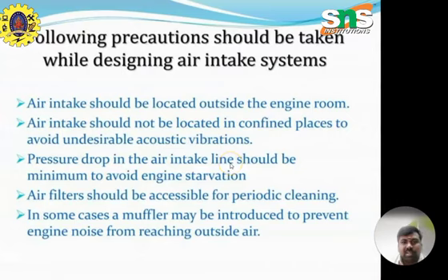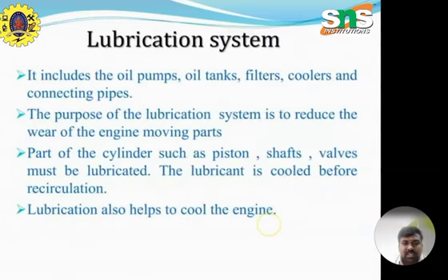The following precautions should be taken while designing the air intake systems. The air intake should be located outside the engine room. Air intake should not be located in confined places to avoid undesirable acoustic vibrations. Pressure drop in the air intake line should be minimum to avoid engine starvation. The air filters should be accessible for periodic cleaning. In some cases, a muffler may be introduced to prevent the engine noise from reaching the outside air.